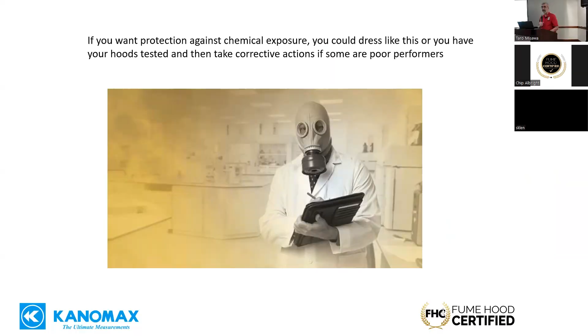So there are two things that you can't see that are important to you. One is the ventilation system, you don't see all that mechanical stuff, the fans on the roof, the air handlers, the VAV valves. But that's very important to the hood performing safely. The other thing you can't see is loss of containment.